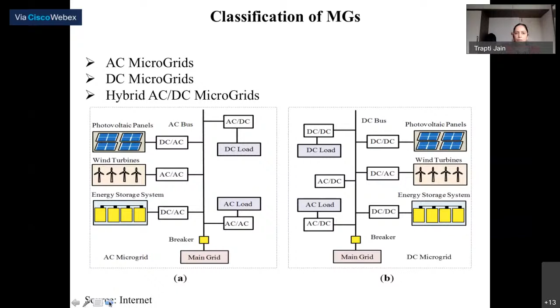Next is the hybrid AC-DC microgrid, which has both types of buses: an AC bus and a DC bus. The plan is that AC loads and AC power generation sources requiring AC power should be connected on the AC bus side via a transformer, while power generation that is by default DC and loads requiring DC power should be on the DC bus side. Both the AC bus and DC bus can be interconnected through a bidirectional AC-DC or DC-AC main converter. This looks like a good concept.